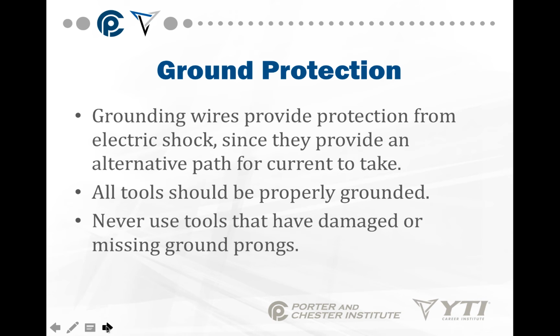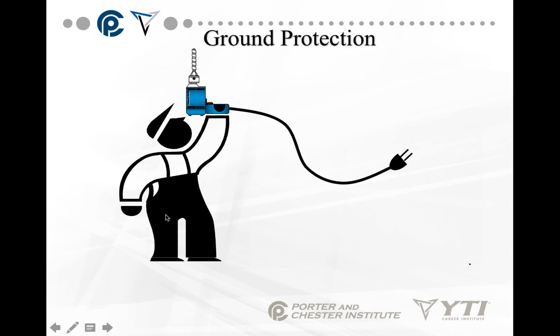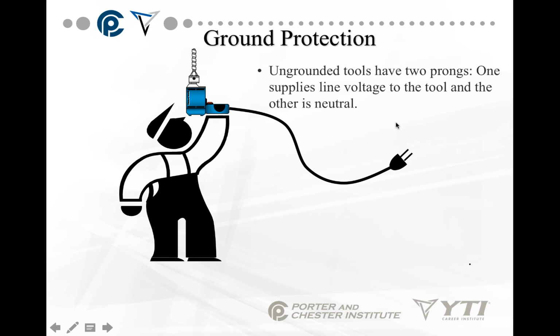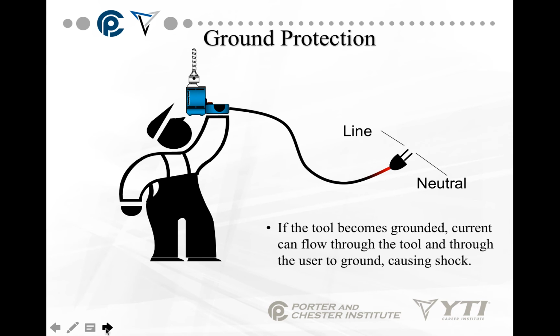In other words, if you come across a tool where a prior technician or someone else has clipped the ground plug off or bent it back to make it fit into an outlet without a ground plug, don't use it. Okay? Ground protection is very important. Okay, ungrounded tools only have two prongs. One supplies the line voltage and the other is neutral. Okay, if that tool goes bad and becomes grounded, the current can flow through the tool and then through you to the ground. Okay, because there's no ground plug on that cord.